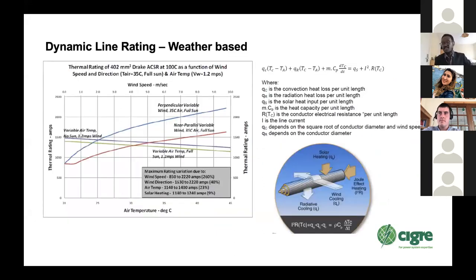So there are several approaches to dynamic line rating. So there are several ways that it can be carried out. One approach involves the use of the weather-based model. Now, in order to employ the weather-based model, what operators or designers do is obtain weather data from wind farms, either in substations or in weather masts close to the line, and the data is then extrapolated along the length of the line.